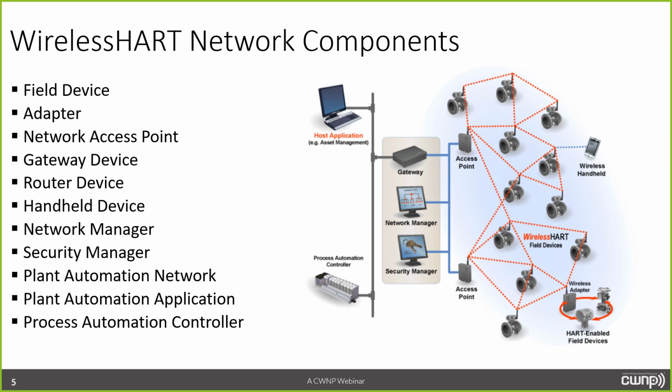So the second thing listed here, the adapter, is the thing that lets a wired field device connect to the WirelessHART network. Now, depending on how you look at the understanding of the language in the specification, you could say that even WirelessHART devices have the adapter. So the adapter is a module, it's a component on the WirelessHART device. But certainly an adapter can be used to connect a HART device to the WirelessHART network.